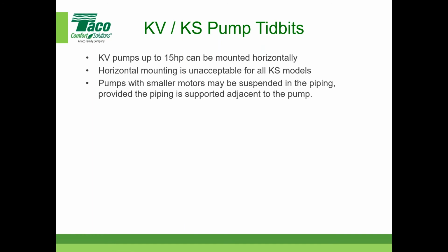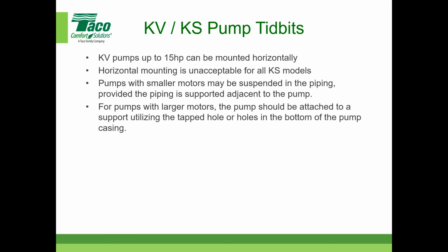Pumps with smaller motors may be suspended in the piping, as long as the pipe hangers are strong enough to support the pump and motor, and are located next to the pump. I'll show you some pictures of that shortly.